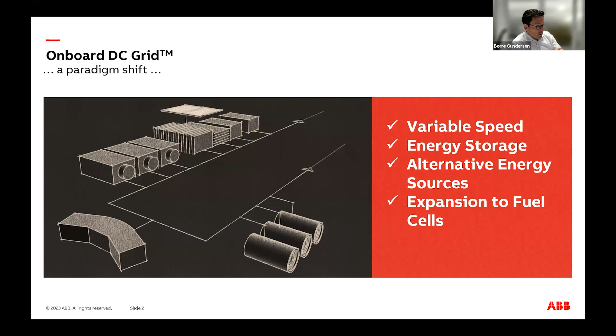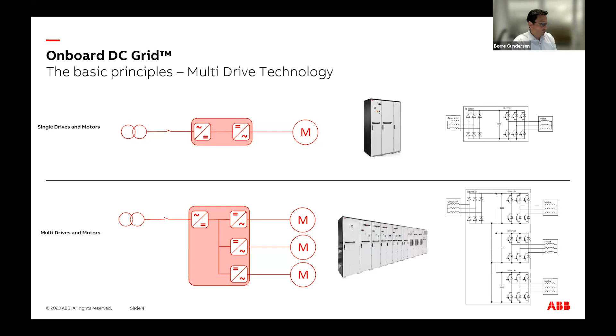So a little bit on the concept itself - probably many of you already know, but I need to touch on it. The basis of a DC grid or DC-based system comes from frequency converter technology, and it's not a new technology as such - it's based on a multi-drive setup. In the 80s and 90s we introduced this, and we've taken that component and introduced more protection schemes to act as a switchboard, along with embedded software for controlling the load flow. But the technology itself is not that new - it's from the 80s and 90s. That's what we're using as a base.